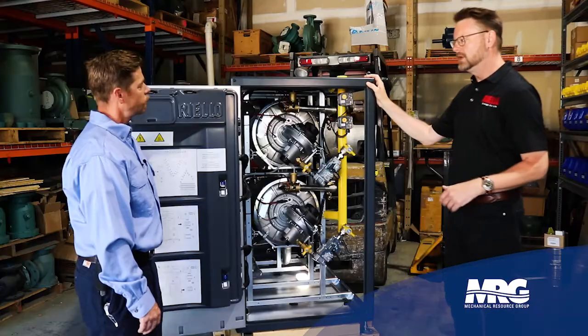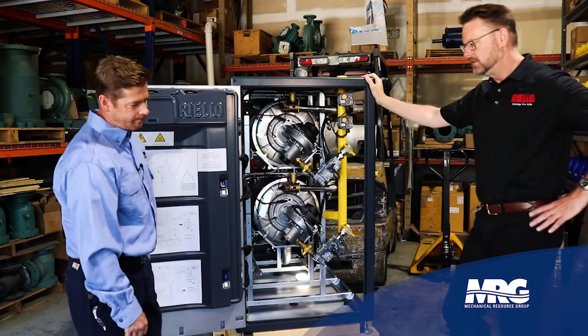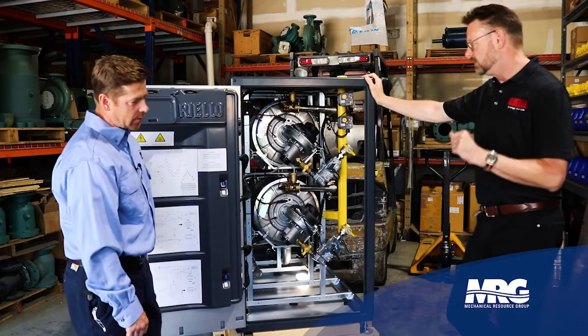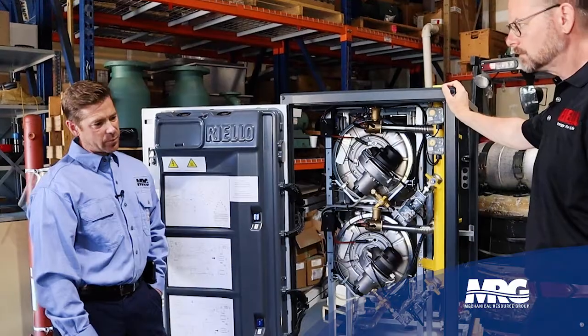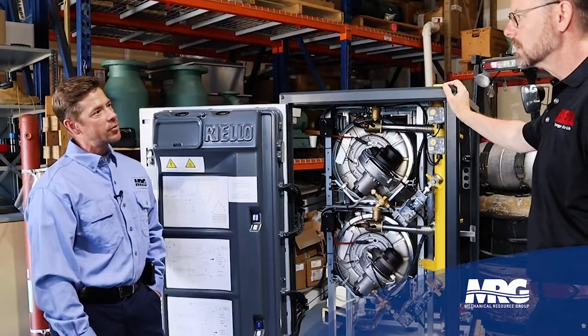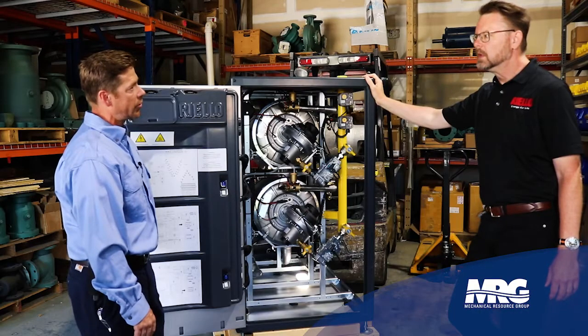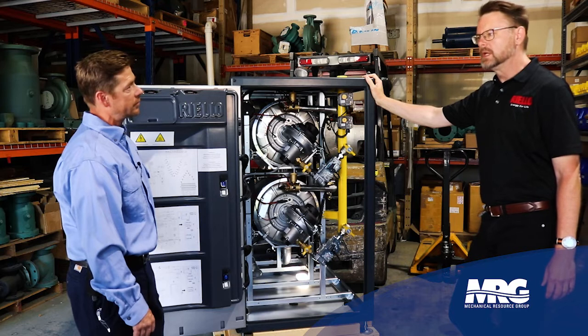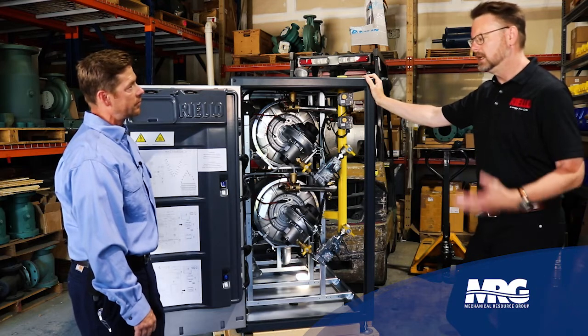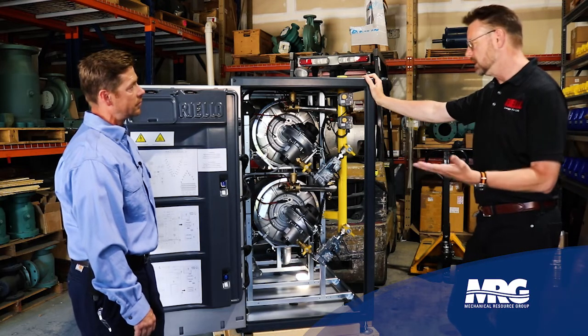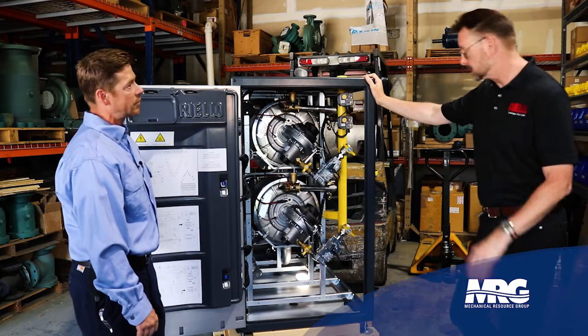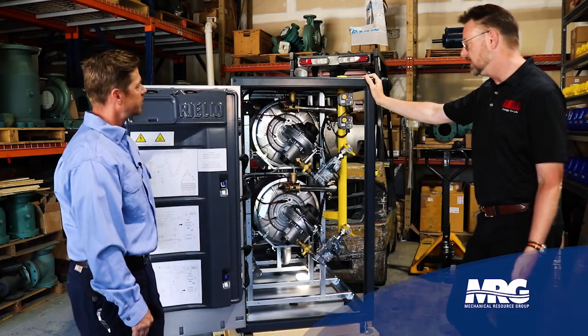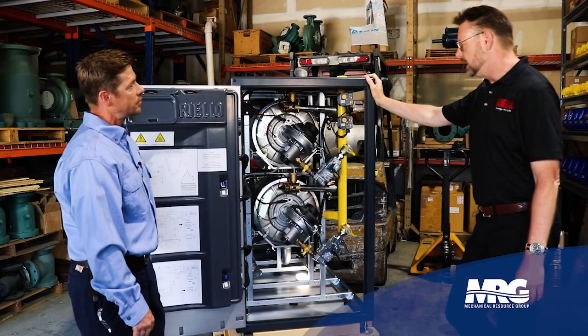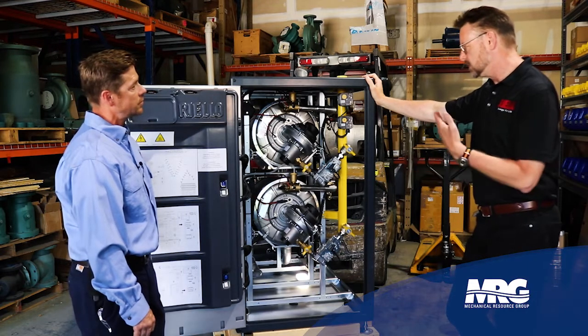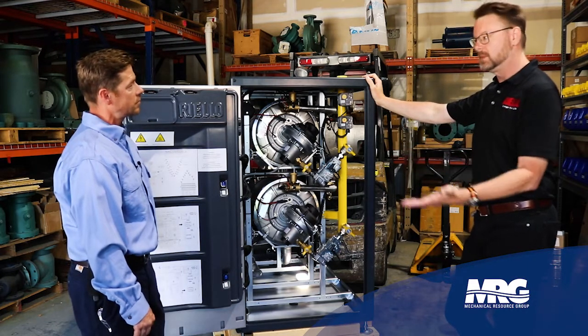What's another issue, Kevin, if you could, that you've run into? We've had ignition issues. We've had flow issues. Is there something else? Just poor heat exchange. Basically, the tube's getting corroded or dirty. Okay, you have a situation where the heat exchanger is beginning to become worn. It's been poorly maintained by somebody else. Right. Just over time has taken its toll, and that manifests in eventual failure or compromised capacity.